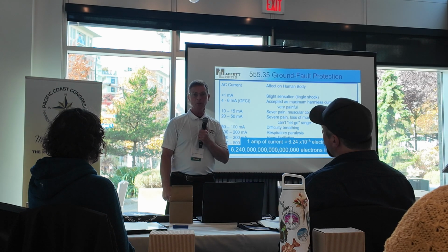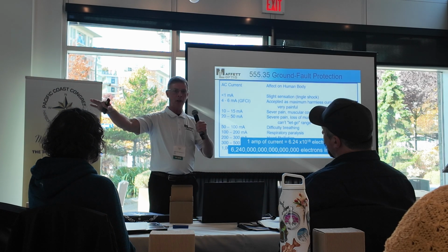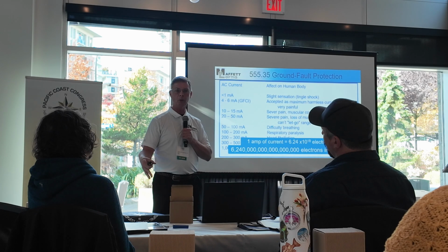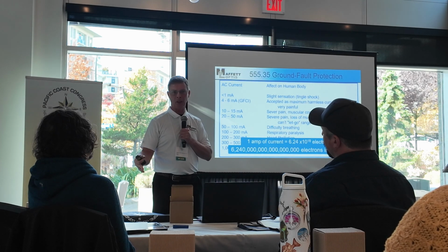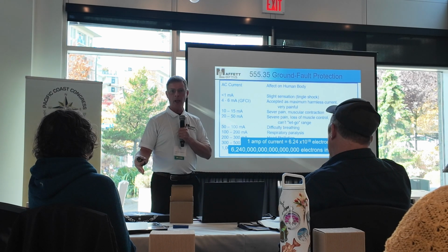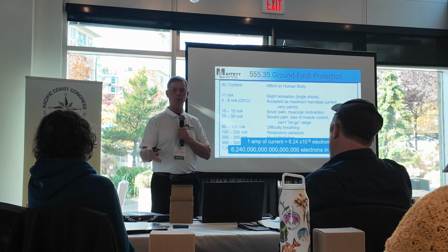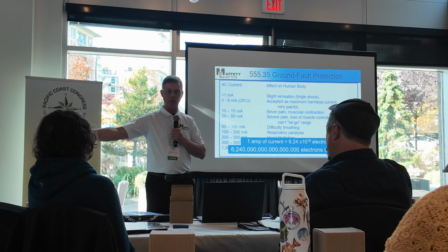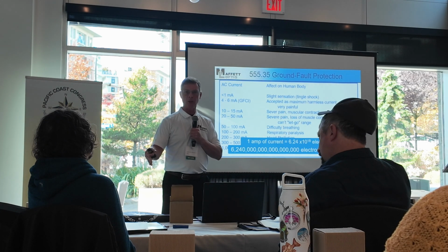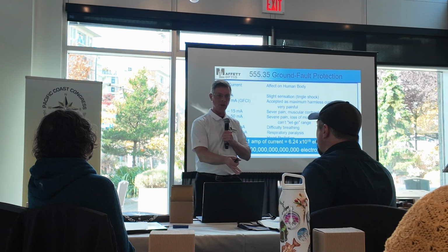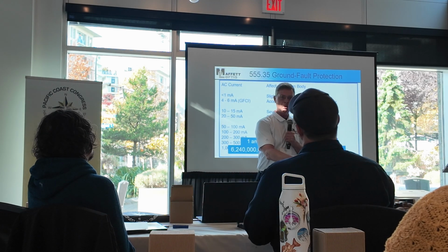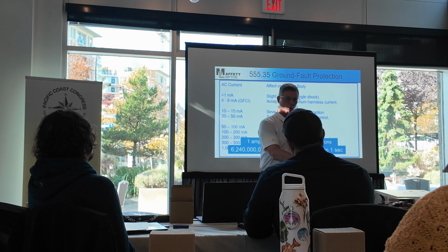Some that I've tested, I had lookouts, and I actually energized the water at 120 volts, had 320-some odd milliamps flowing, and this one detector said it detected up to 60 feet. So I went out about 70 feet, didn't detect it, went in to 50 feet, didn't detect it, 40 feet, 30 feet, 20 feet, 10 feet, would not detect it. It would not alarm. I moved in about 4 or 3 feet, then it started barely ticking up, and at about 2 feet it fully alarmed, pulling 300 and some odd milliamps of leakage current.